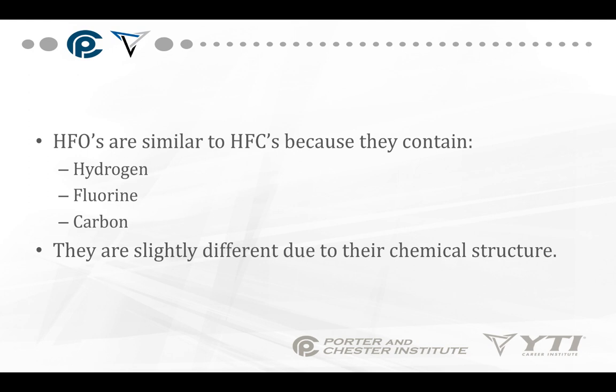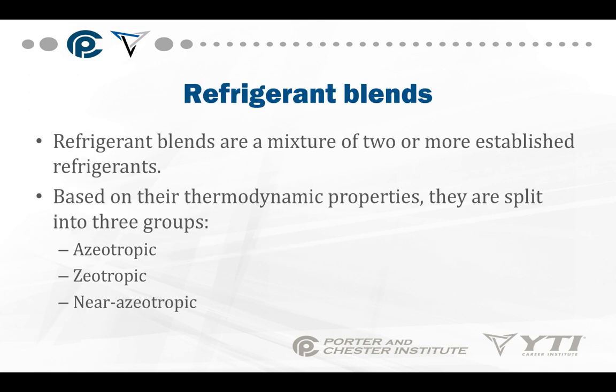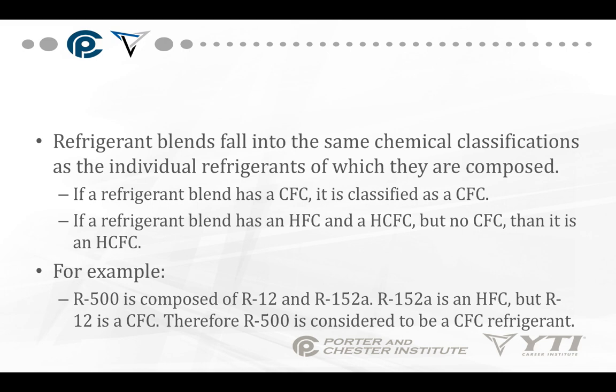HFOs are similar to HFCs because they contain hydrogen, fluorine, and carbon, but they're slightly different due to their chemical structure. Refrigerant blends are a mixture of two or more established refrigerants — they have to be done in a factory environment, not by the technician. Based on thermodynamic properties, blends are split into three groups: azeotropic, zeotropic, and near-azeotropic. Refrigerant blends fall into the same chemical classifications as the individual refrigerants they're composed of. We use the harshest classification for blends containing one or more different classifications.